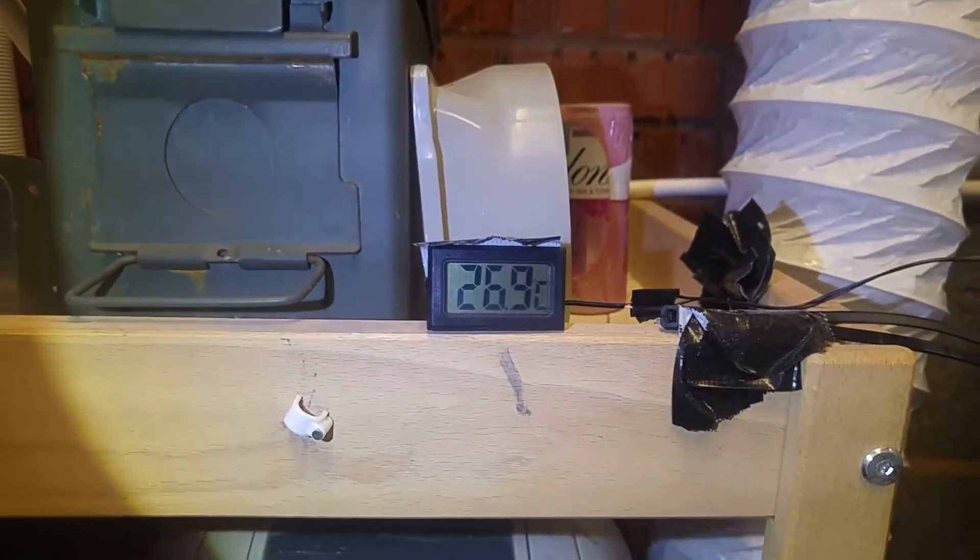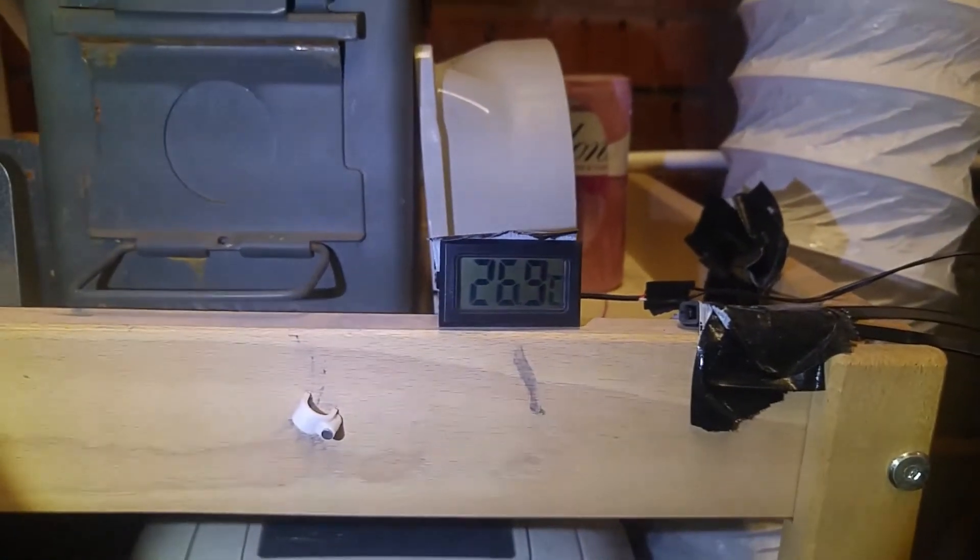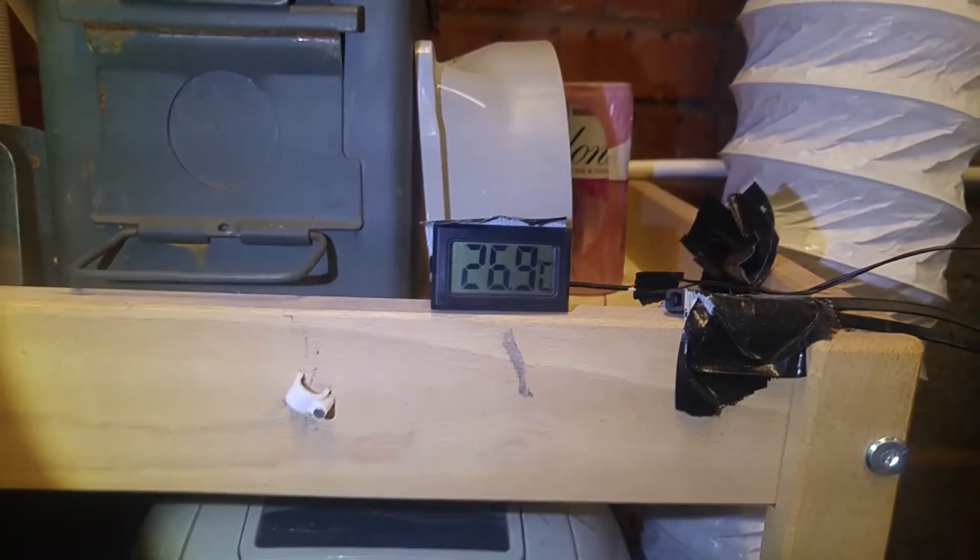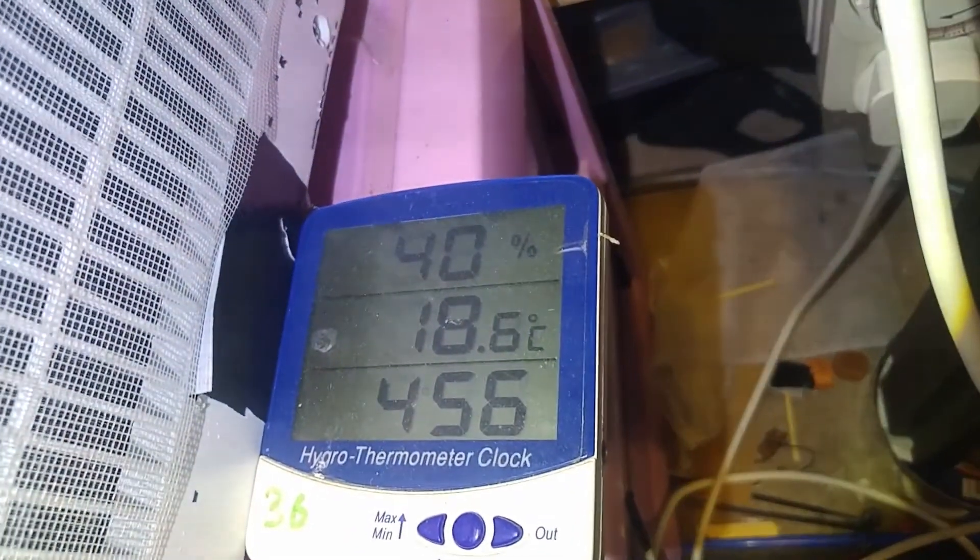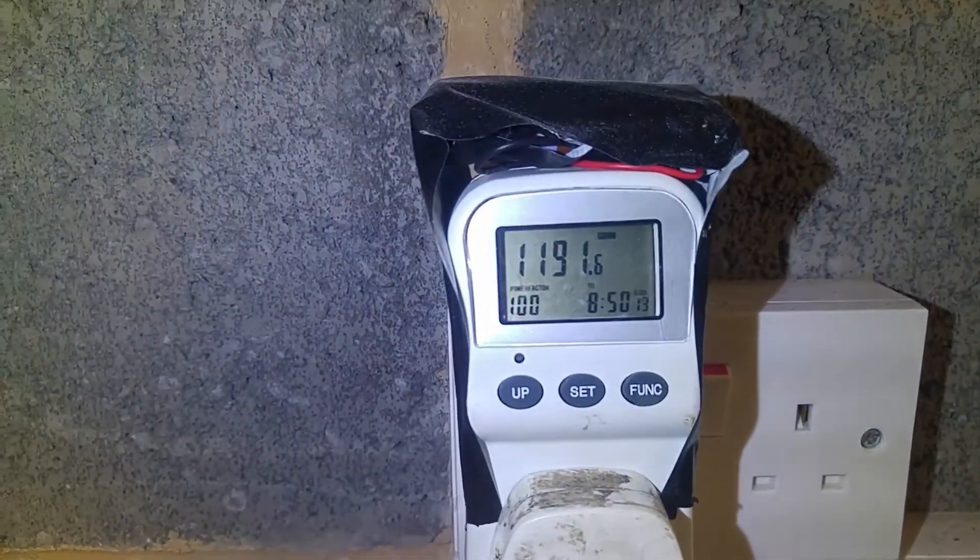So five minutes has passed and it seems to have stabilized now. So we've got 27 degrees coming out, 18 and a half degrees going in, and power consumption is just over a kilowatt.